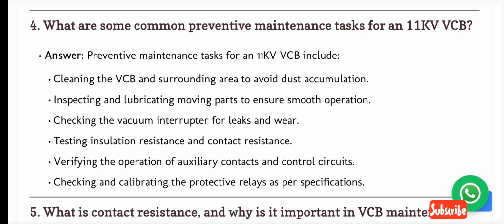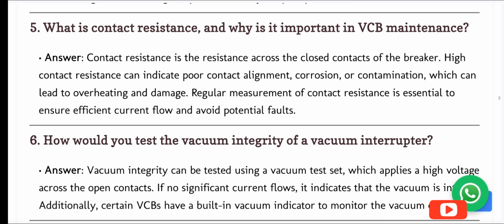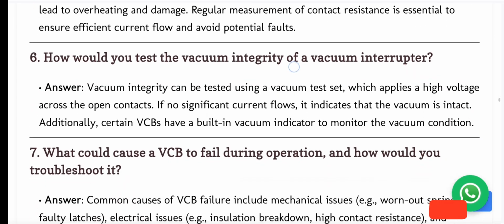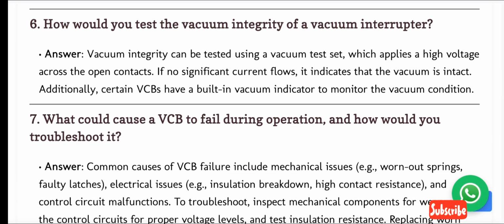5. What is contact resistance, and why is it important in VCB maintenance? Answer. Contact resistance is the resistance across the closed contacts of the breaker. High contact resistance can indicate poor contact alignment, corrosion, or contamination, which can lead to overheating and damage. Regular measurement of contact resistance is essential to ensure efficient current flow and avoid potential faults. 6. How would you test the vacuum integrity of a vacuum interrupter?